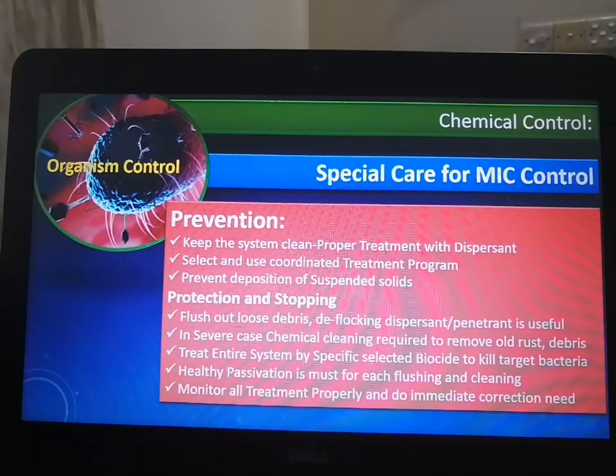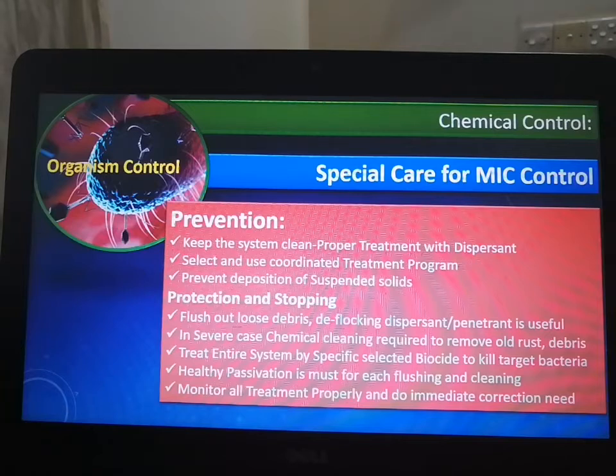We can't allow slight deposits, slime, suspended particles, or any kind of fouling, because if fouling is present there is a probability of MIC. So we have to include dispersion in our treatment, and we should have a coordinated treatment program.